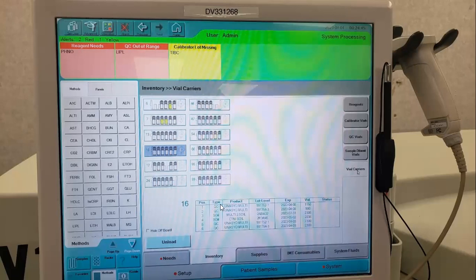So we have QC and dilutant, and then it will list the product, what lot level it is, when it expires, and the volume. I like to keep an eye on the volume and the expiration date specifically. If it's getting close to expiration, there are some that degrade a lot faster than others, so it is a good idea to remove those before we get into QC. Typically, anything that is yellow, we will take off the machine and replace, and if it is red, we will also take it off the machine and replace.